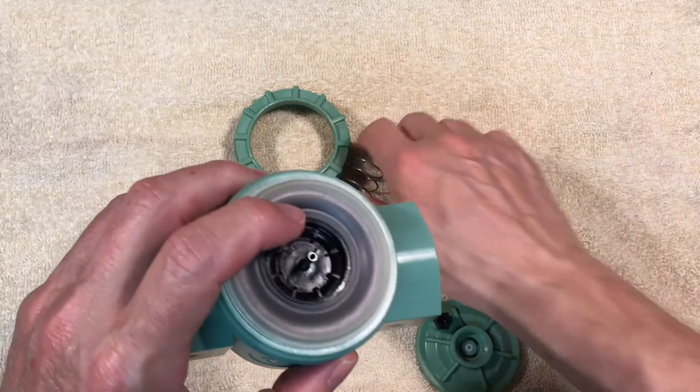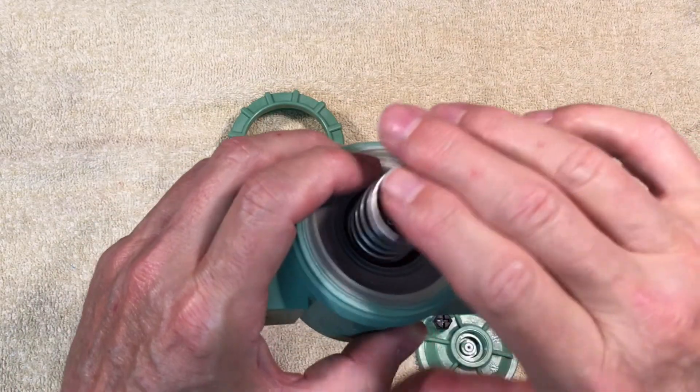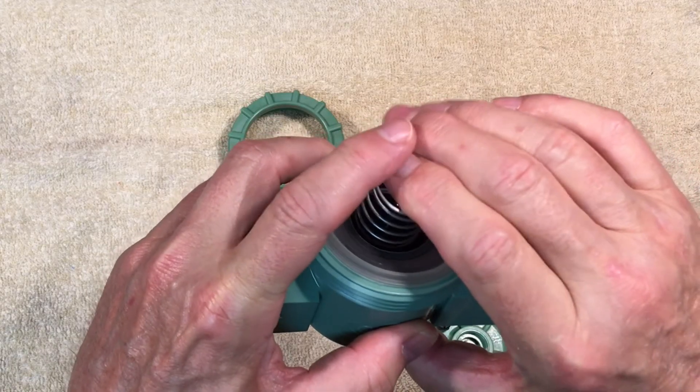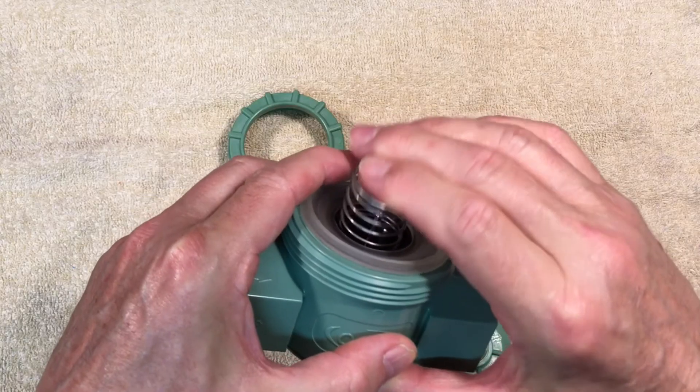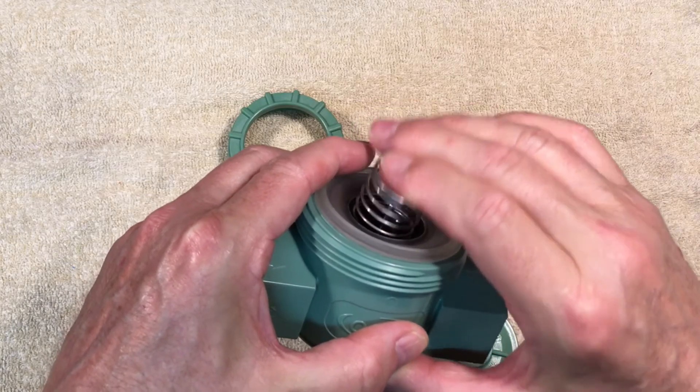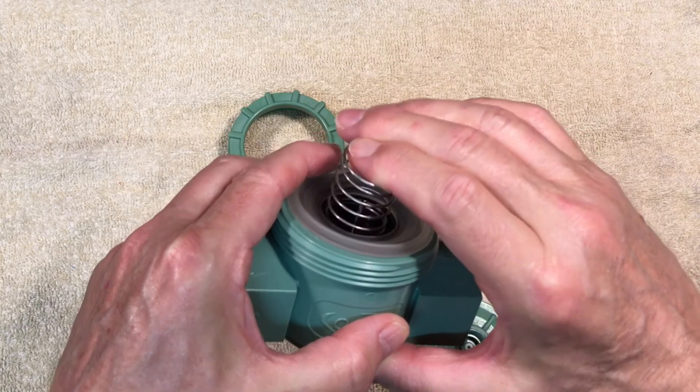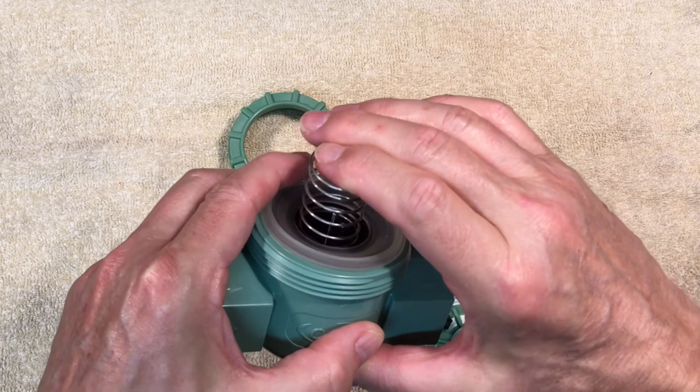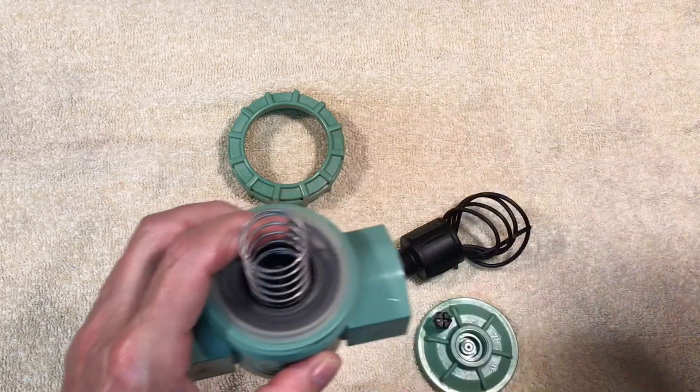The spring assists in keeping the diaphragm down and also makes sure the diaphragm returns completely to the down position when the solenoid is de-energized. Once the pressure is the same under the diaphragm and over the diaphragm, there is no force acting on it to move it up or down. The spring helps to make sure the diaphragm returns to the off position when the solenoid is turned off.